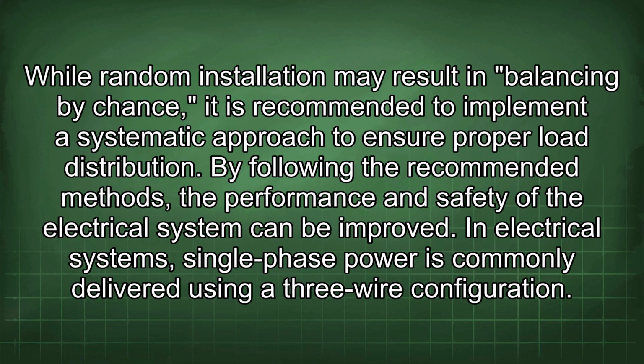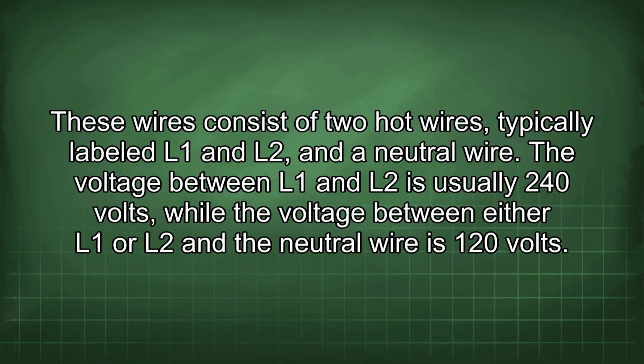While random installation may result in balancing by chance, it is recommended to implement a systematic approach to ensure proper load distribution. By following the recommended methods, the performance and safety of the electrical system can be improved. In electrical systems, single-phase power is commonly delivered using a 3-wire configuration. These wires consist of 2 hot wires, typically labeled L1 and L2, and a neutral wire. The voltage between L1 and L2 is usually 240 volts, while the voltage between either L1 or L2 and the neutral wire is 120 volts.